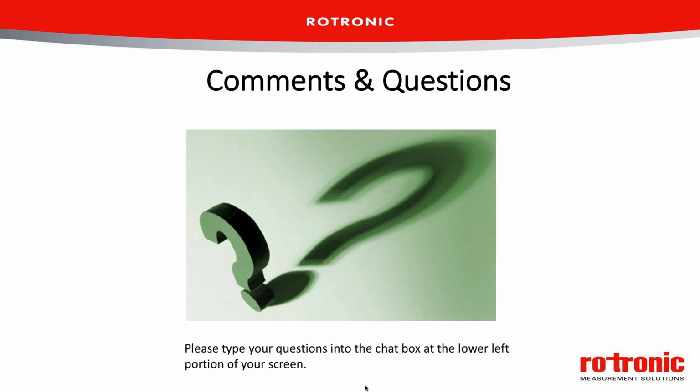Our next question comes from Patricia. She asks, if storage racks are near loading docks, how do you determine how much mapping should be done with doors open versus doors closed? Good question. If the warehouse is operating, then what you would do is run the mapping for, typically the industry does it for a week.